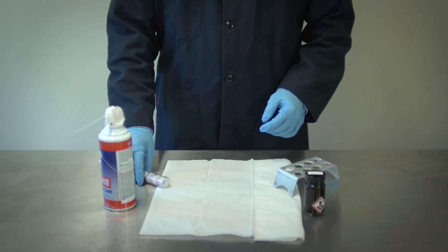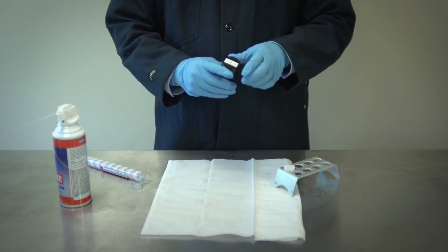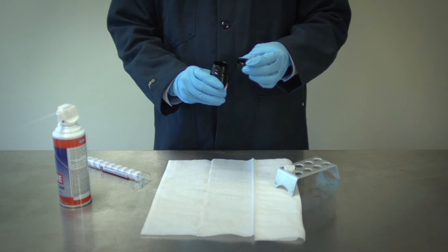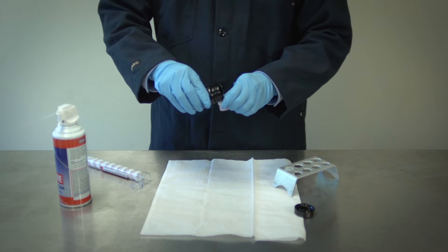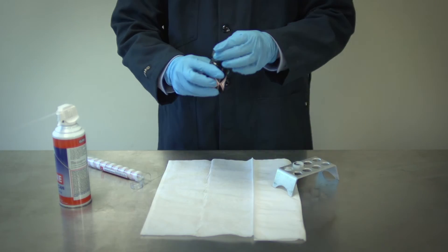The SINDIE analyzes samples directly without the need to combust or alter the sample. The instrument requires no changes in mechanical setup or sample presentation when switching from light samples like gas or diesel to heavier samples like crude oil or bunker fuel.